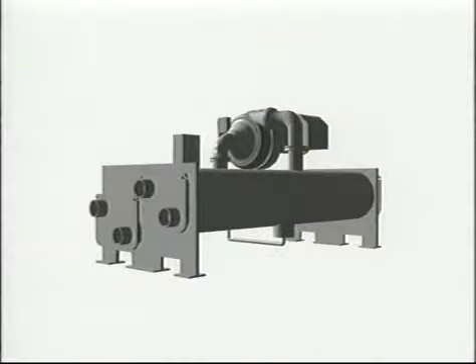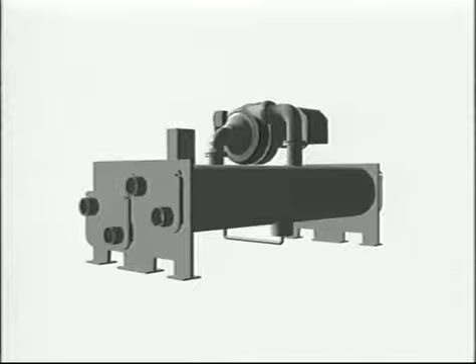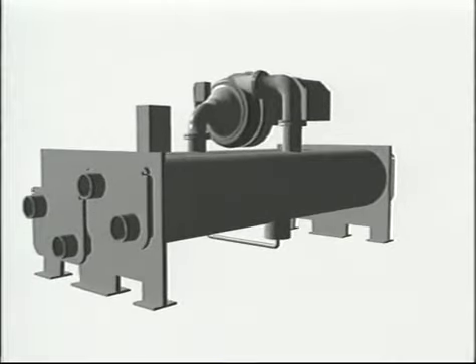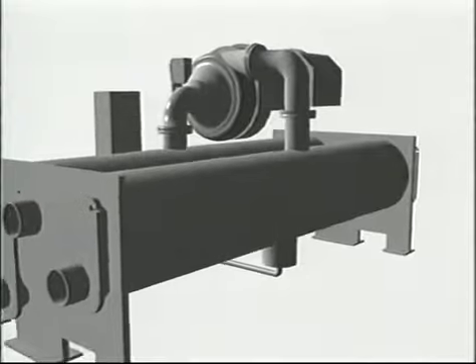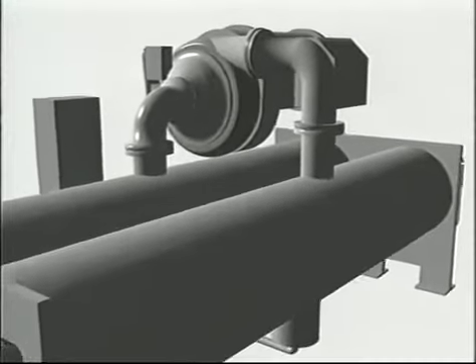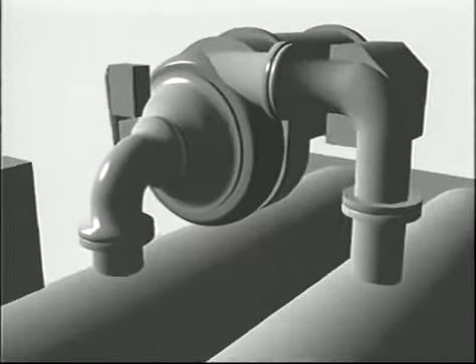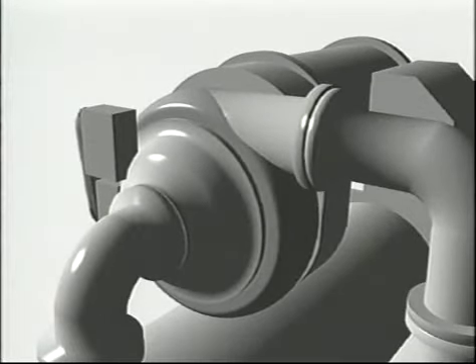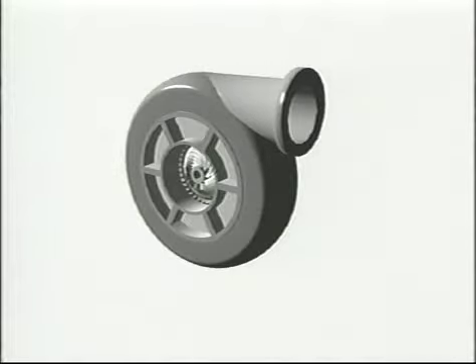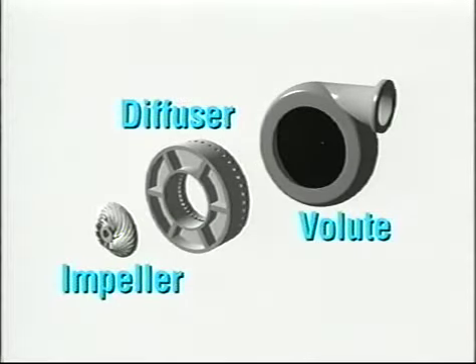Now let's take a closer look at what goes on inside your chiller. Centrifugal compressors are non-positive displacement compressors. These compressors obtain compression without reducing the internal volume of the compression chamber. They are suitable for compressing large amounts of refrigerant and normally are used in very large capacity cooling systems. A centrifugal compressor is a relatively simple mechanism. Its basic components are an impeller, a diffuser, and a volute casing. Large tonnage centrifugal compressors may have two or more impellers or stages in the same casing.